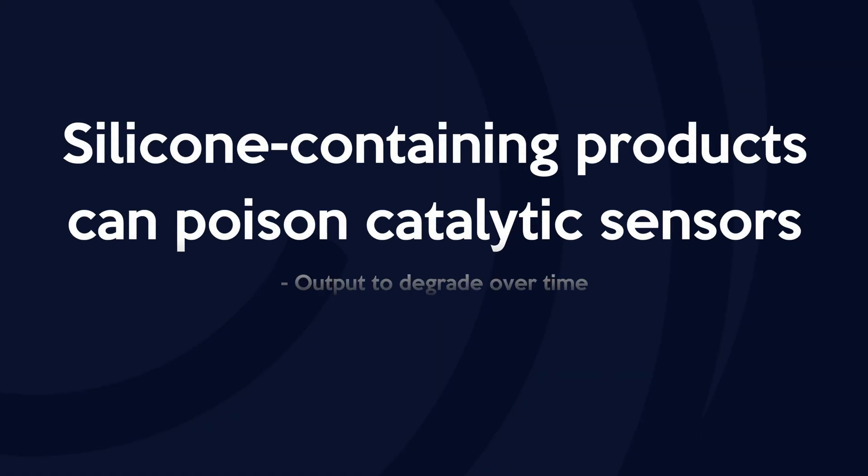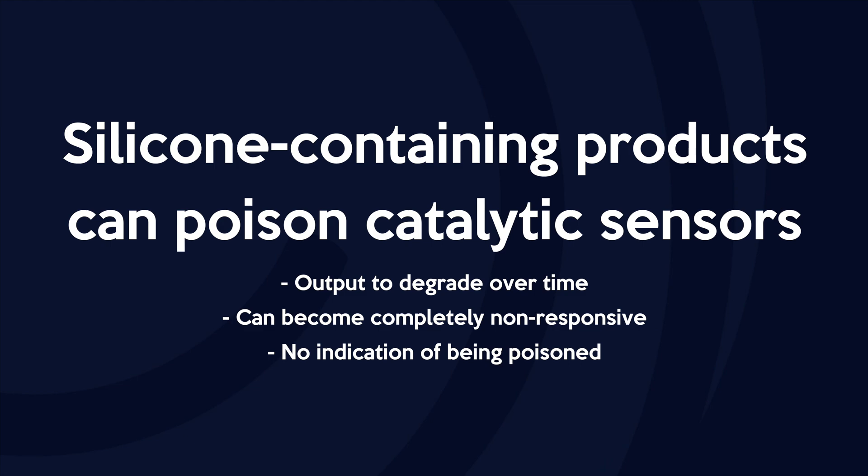Silicone-containing products can poison catalytic sensors causing their output to degrade over time and even become completely non-responsive. After poisoning, catalytic sensors give no indication of being poisoned, which puts the safety of the end user at risk.